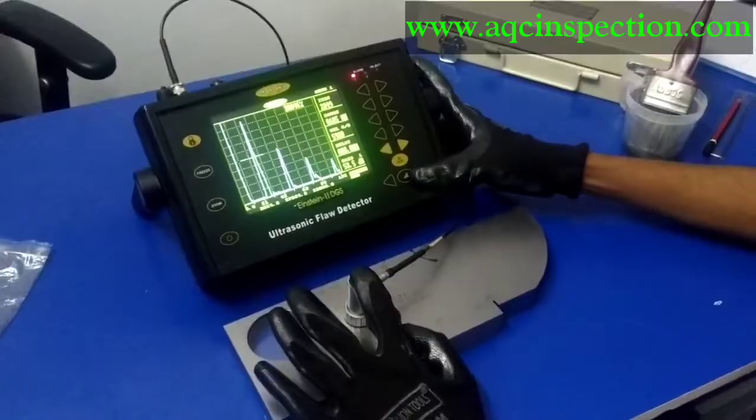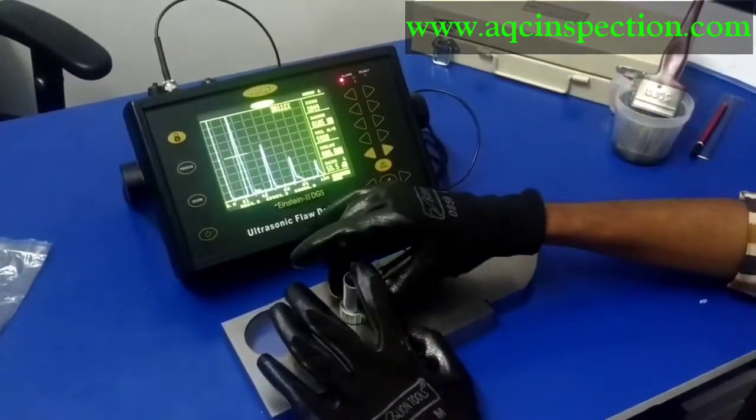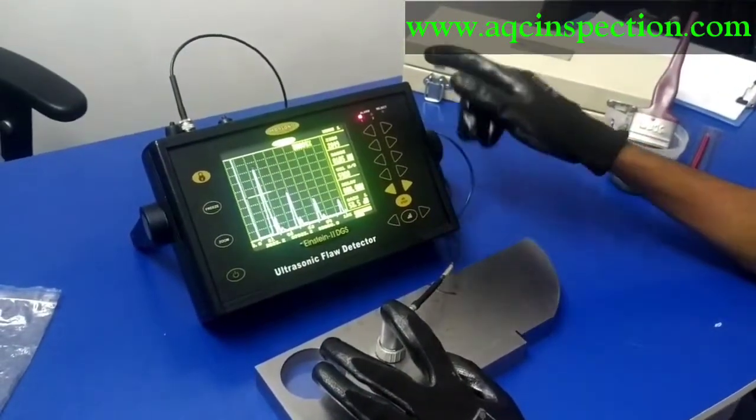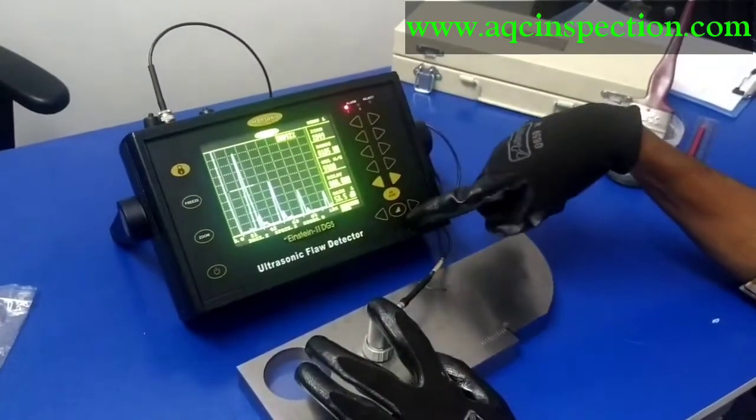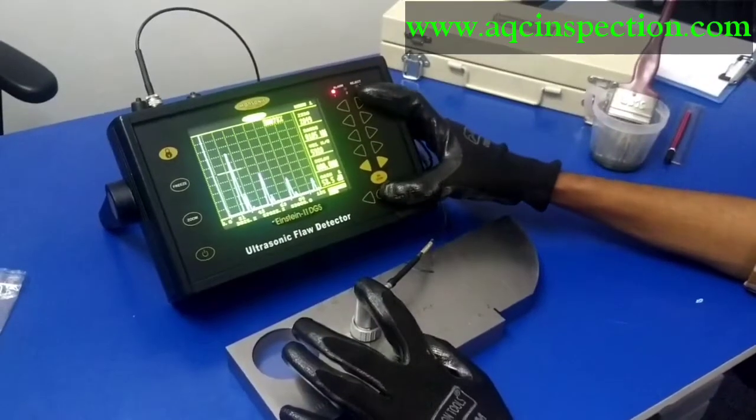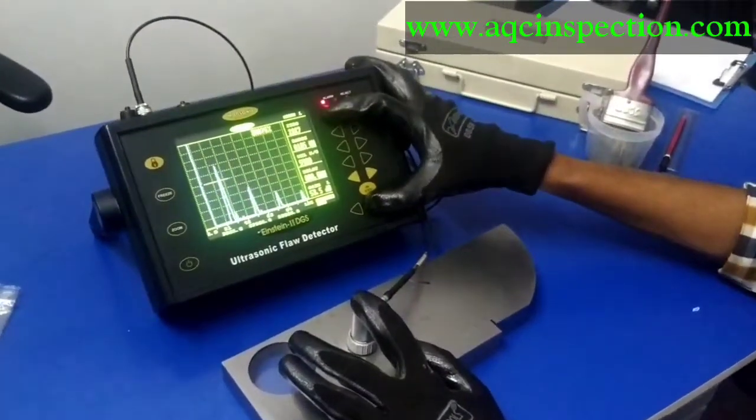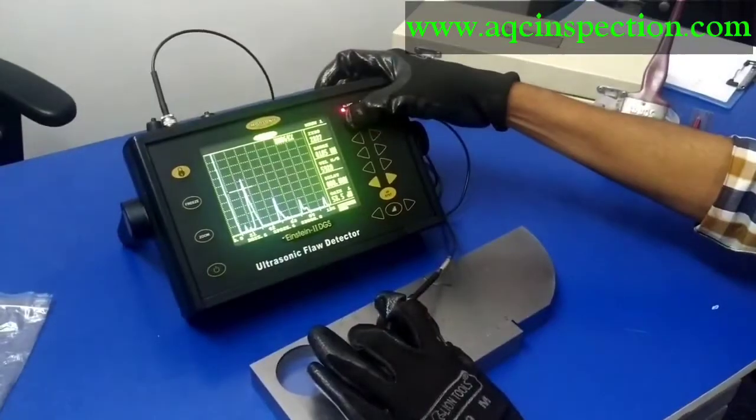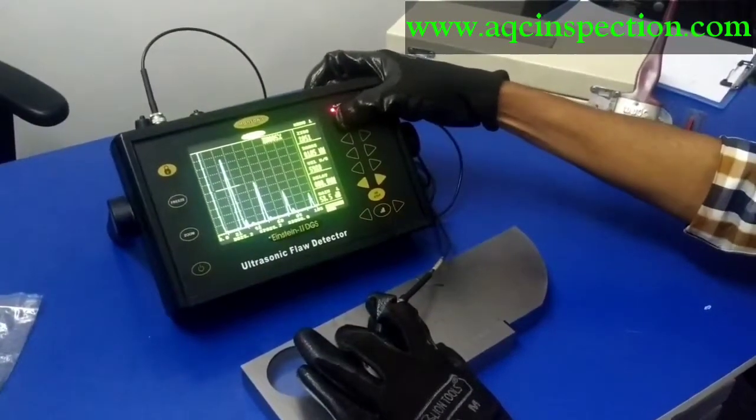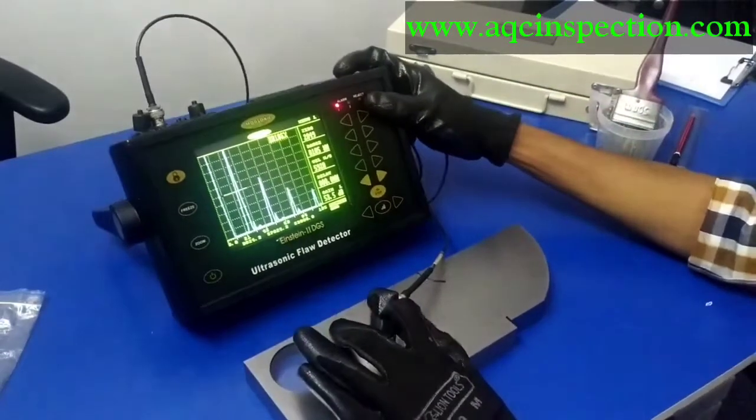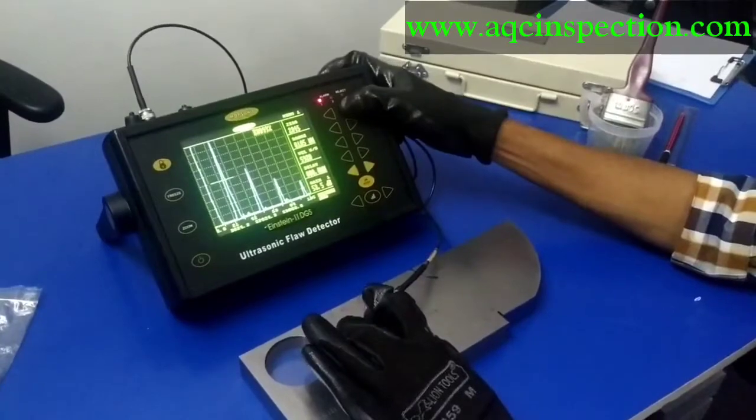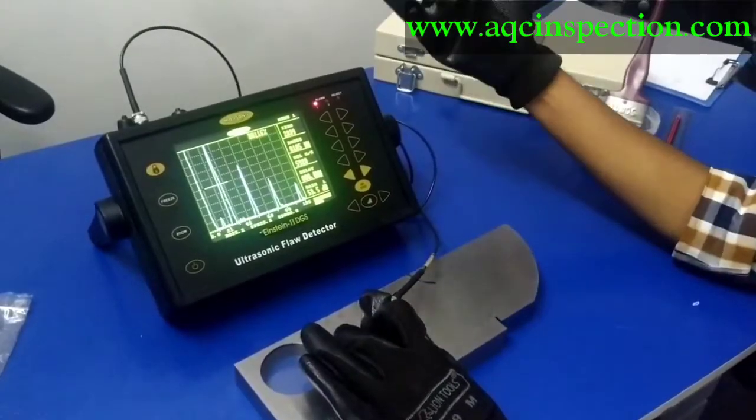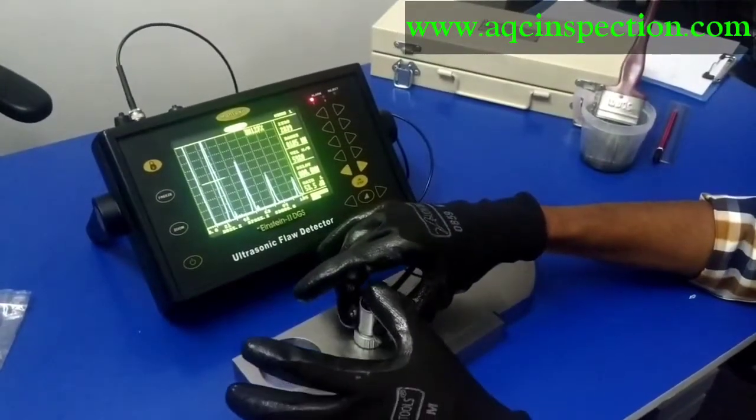I am going to adjust the probe zero so that I will get 25 mm as my first backwall. This key right here is called the hard key which is used for moving the values faster. So I am going to set this backwall at 25 mm. Already it is 26.